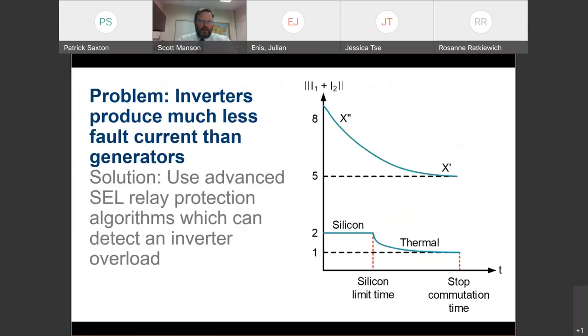Not only are the currents anomalous in their time domain, but in their amplitude. Here's an example in this plot. On the x-axis is time. On the y-axis is the net sum current produced by either the IBR on the bottom or a generator on the top. These are equally sized distributed energy resources. One is a generator, a synchronous machine, on the top. The second on the bottom is an inverter-based resource. An inverter is seriously limited in its ability to produce current because the silicon is not capable of producing the 8 times or 10 times currents during a fault that a generator has for the last 100 years.